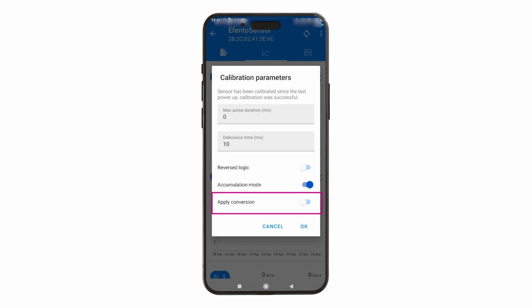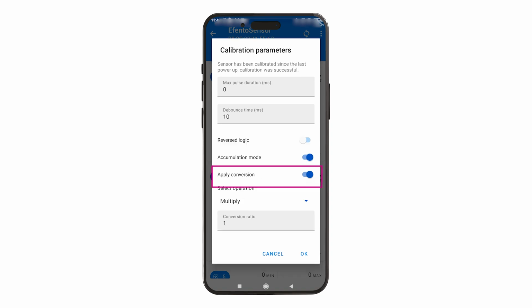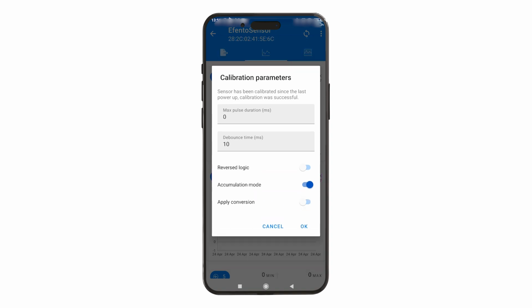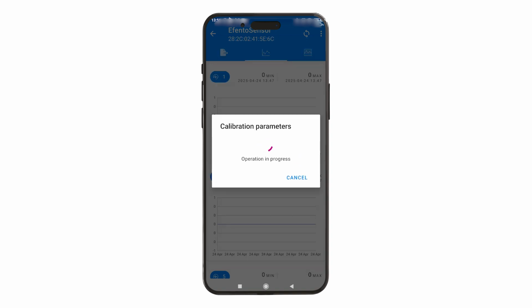Conversion ratio allows for multiplying or dividing the number of pulses received at the sensor's input. For example, if you are interested in counting kilowatt hours and you know that the electricity meter generates 100 pulses per kilowatt hour, you can set the conversion factor to divide by 100. This way, the pulse counter reading will increase only after receiving 100 pulses at the counting input. It is important to note that the configuration is done individually for each of the 3 available measurement channels.